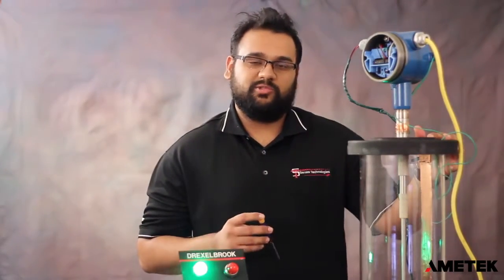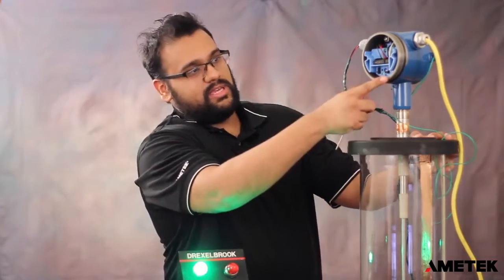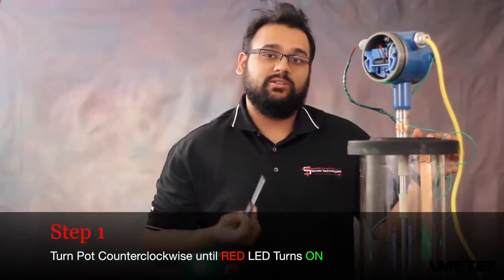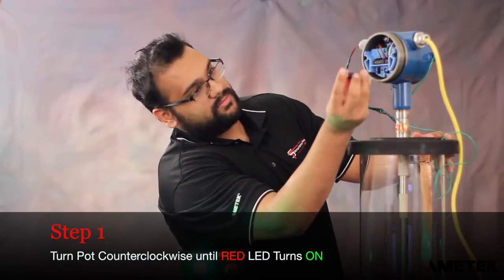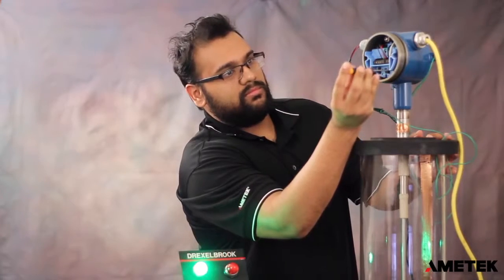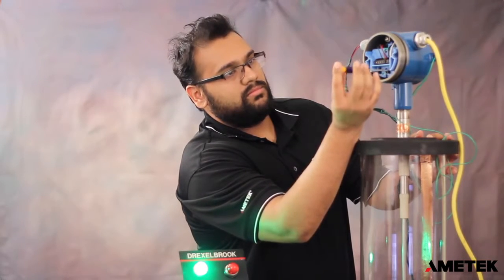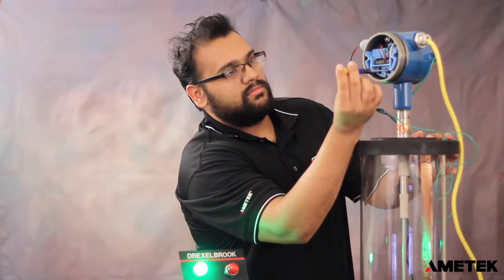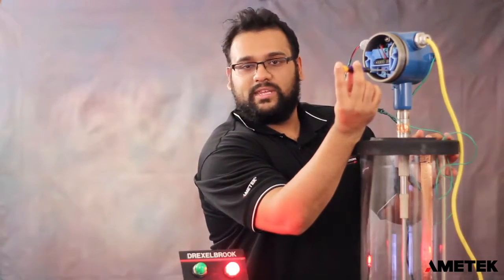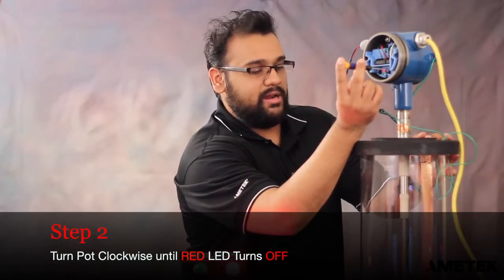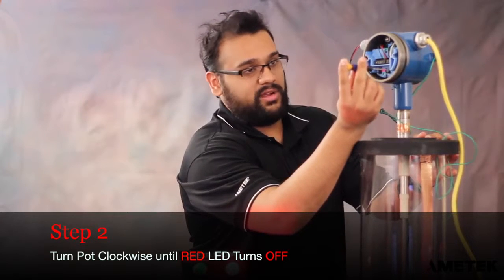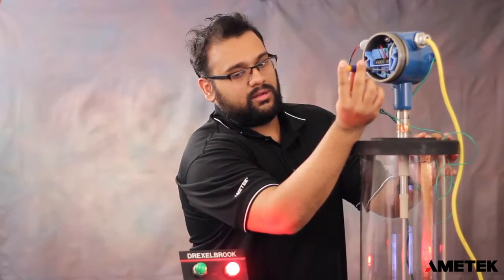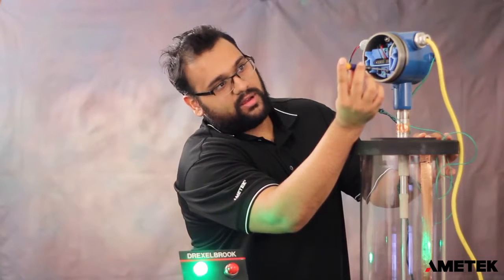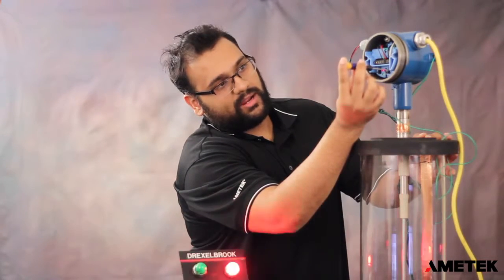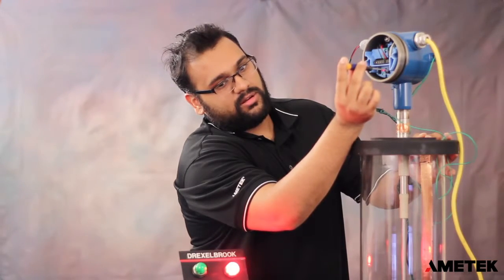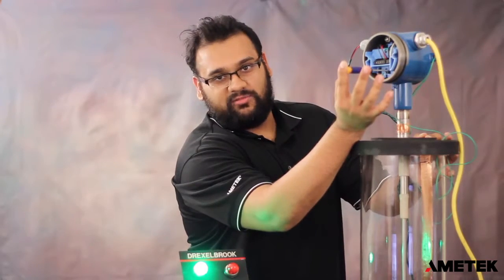Okay, so the first step in our calibration procedure is you're going to take your screwdriver and turn the sensitivity adjustment fully counterclockwise until the red LED turns on. Okay, now that the red LED has turned on, we're going to turn the adjustment pot clockwise until the red LED just turns off. So turn slowly, and it turns off. And I'm going to go back again just to show. This area right here is known as your trip point. So now we have it in the off position.